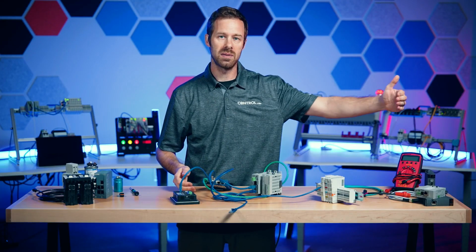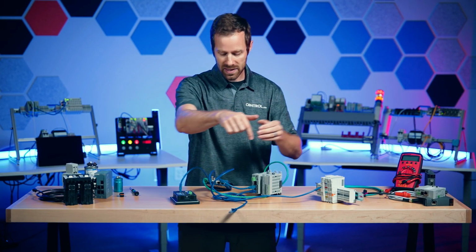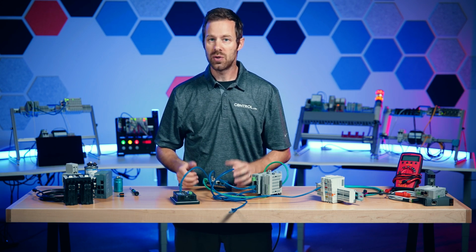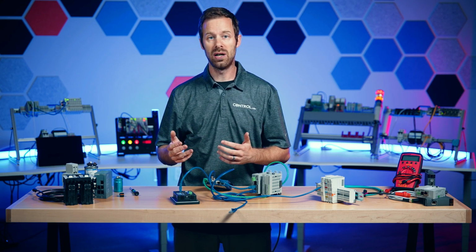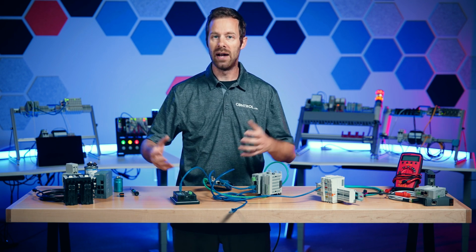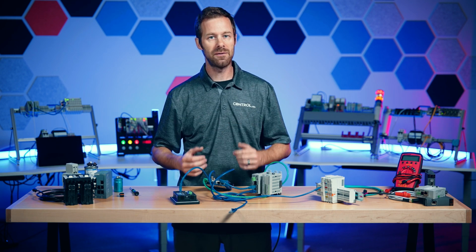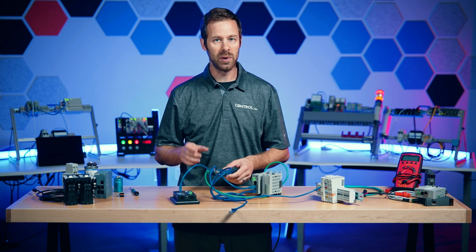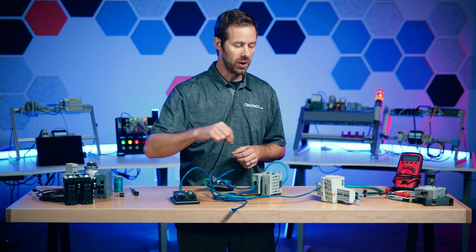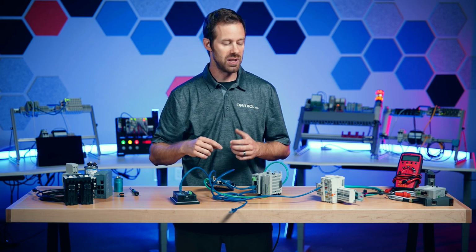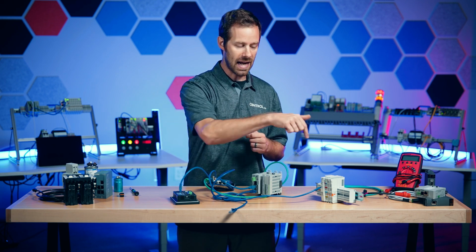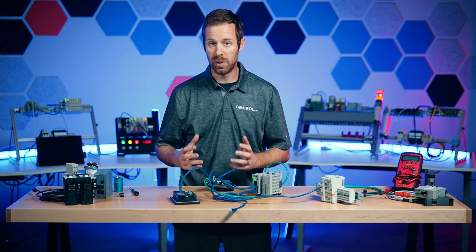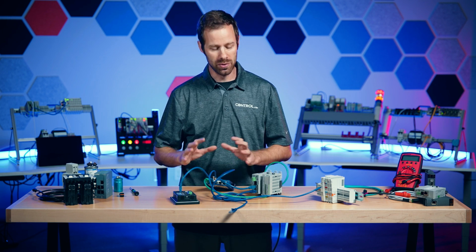but the larger our system gets, we connect more and more devices, and we find that we're actually using fewer network connections on our switch. So that's the difference between ring and star. Star is a much more typical network where everything is connected back to a central point, easy for organization and finding all of our signals, but it's not so great for reliability, where if we lose one signal. This ring level topology allows us redundancy, and if a wire breaks, we still have a solid connection route between all of our devices. We can find that broken cable, and we can repair or replace it without losing our entire network.